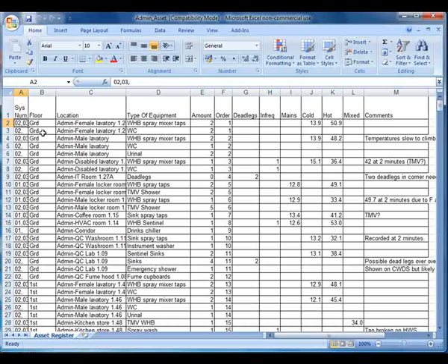Remember the system identifications we gave to each water storage system from the system ID spreadsheet? Well, it's important in here to record the system identification that's responsible for feeding the type of equipment that you're talking about. So if I took this particular example here, we've got a WC and I've recorded that it's fed via system ID 02 and it needs a comma after it. I called the system ID 02 when I filled out the system identification sheet, so it needs to be called 02 in here and not just 2.